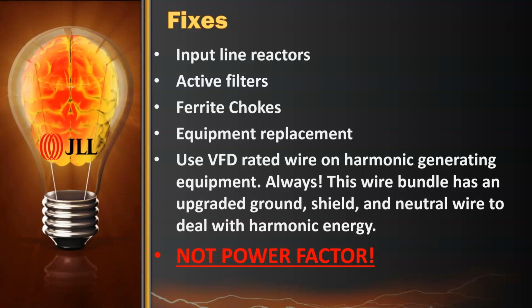Okay. Is there specific equipment we should be looking for in a hospital environment outside of central plant building systems? Oh yeah. So what about radiology, MRI machines? What in hospitals are typically causing harmonic issues? Yeah, anything with a lot of electronics in it. Those are high speed switching devices like an MRI or an X-ray, anything in radiology. Any of those things are producing a large amount of harmonic energy. And yeah, you'll see it at the MRI and at the X-ray machines, radiology, things like that. And if you put a choke on the power feed to that, you're not going to affect it at all. They won't even know it's there. Right. Machine won't know. Yeah. Sure. Right. Because that's a machine you don't want to break.